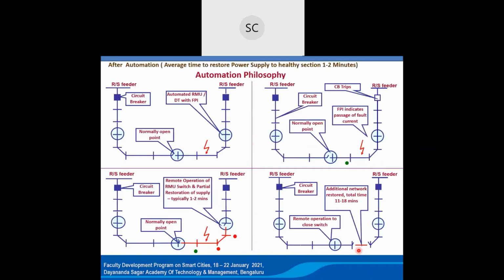in the field. Maybe due to some temporary fault like a tree falling on that one. So what happens? Short circuit, it will trip the relays and breaker. Auto recloser will trip. Temporarily, whatever section is associated with that auto recloser, all customers will lose power. And this programming of 3 shots and the time interval between each shot can be done. Maybe 2 minutes, 5 minutes, we can give like that.